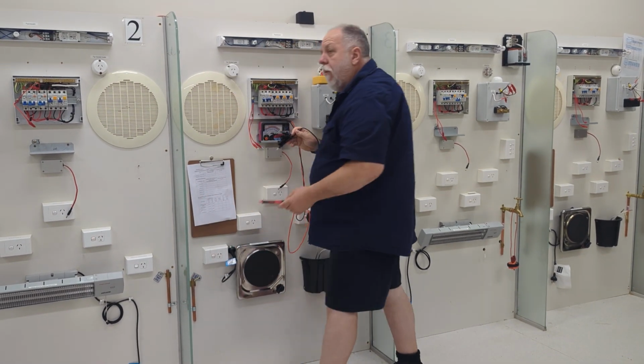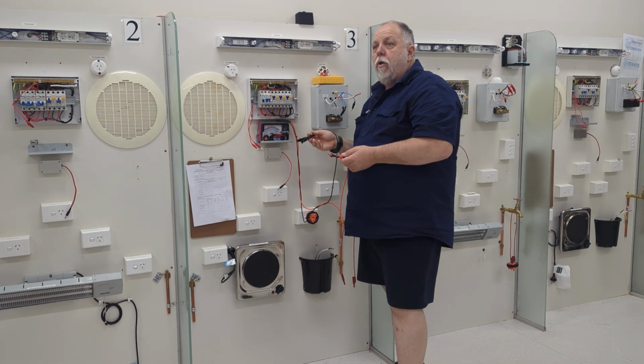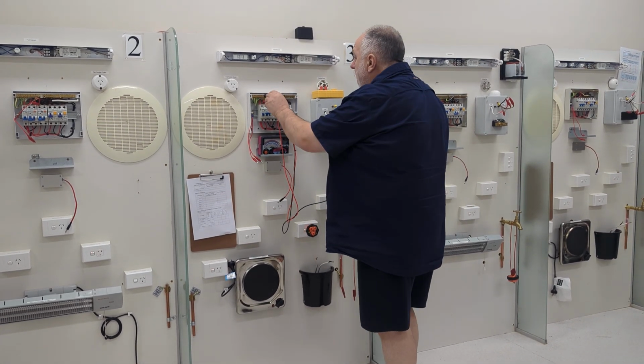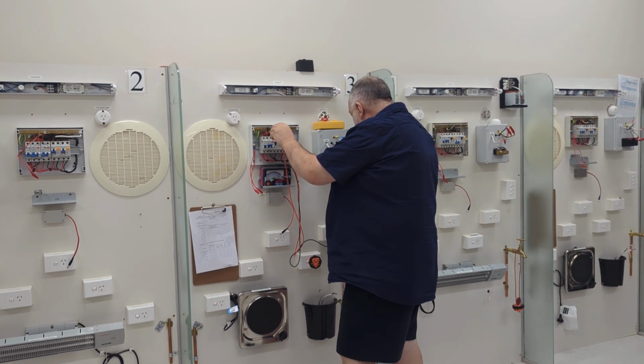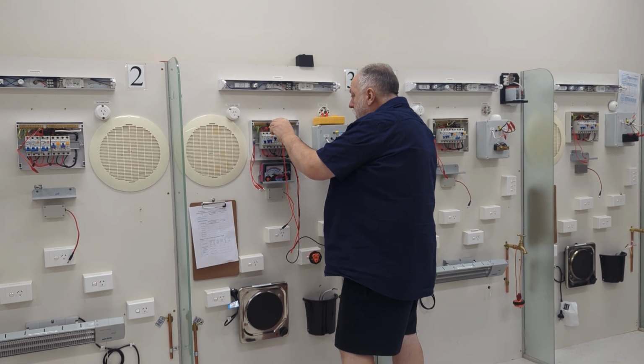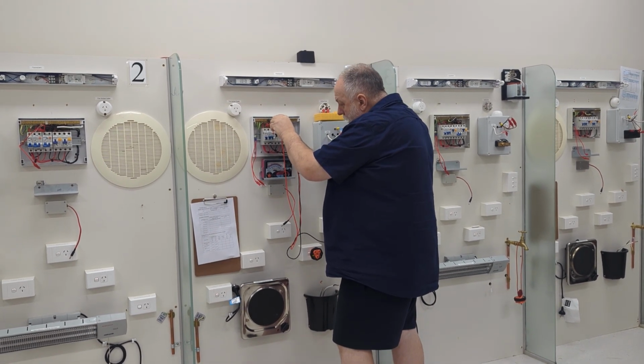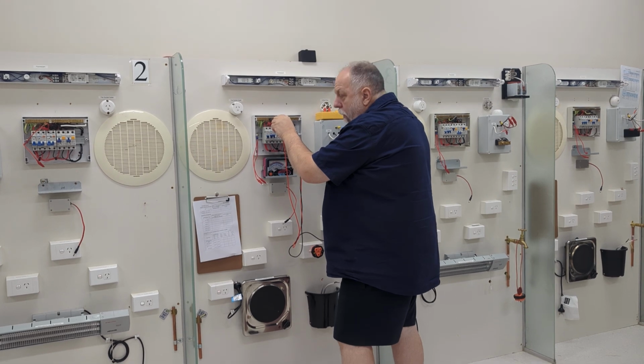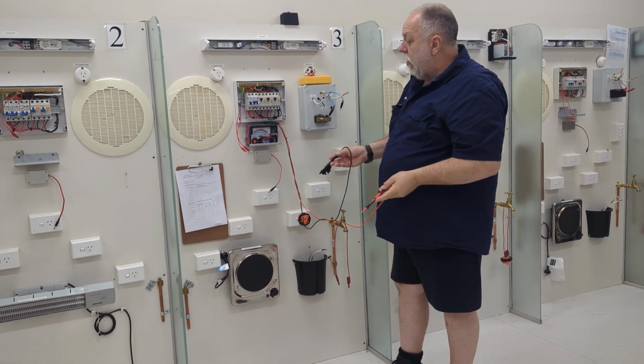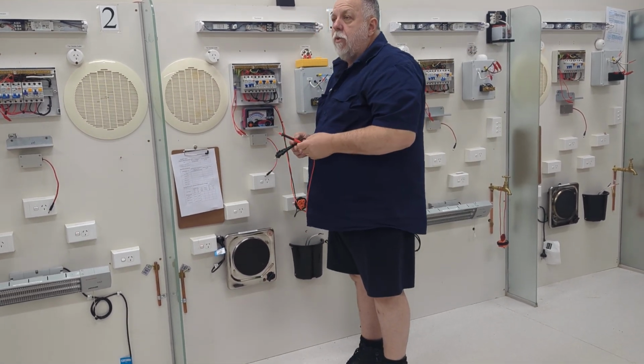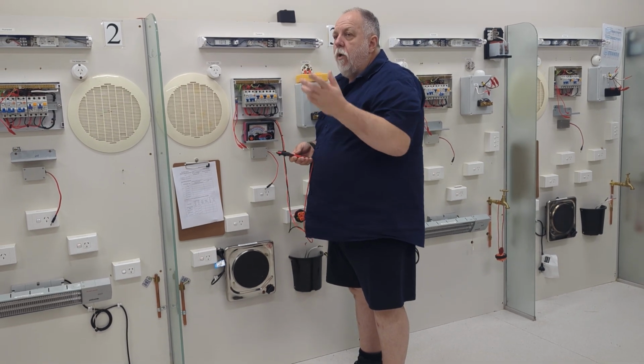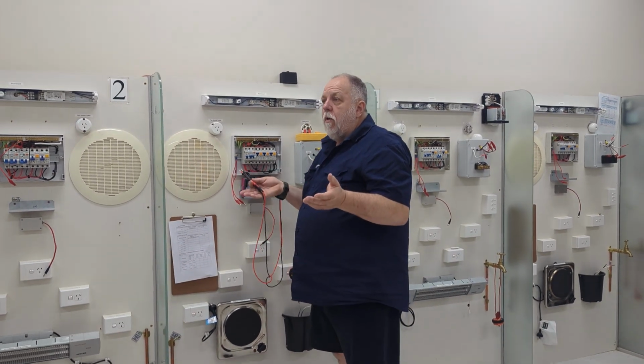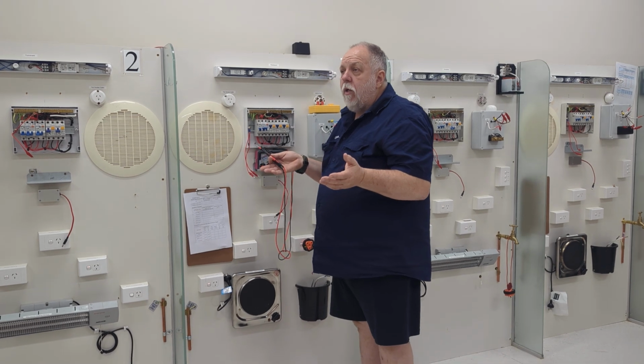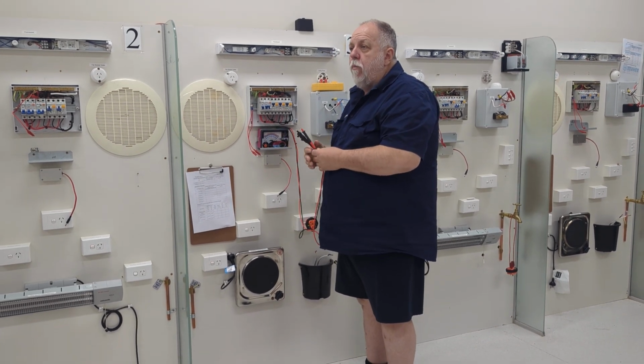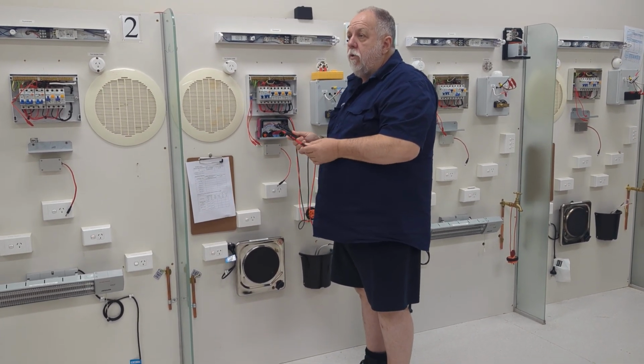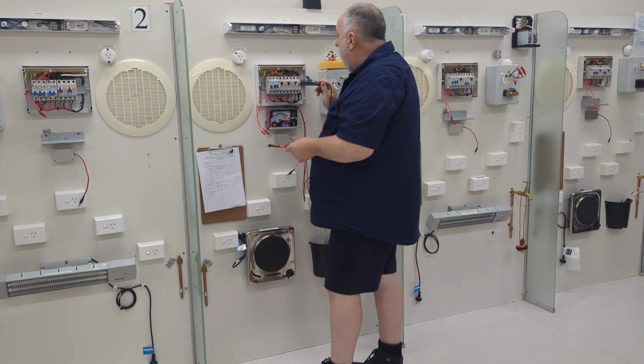I'm getting nothing there. That tells me that I've got an open circuit, there's nothing there. Now I'll go from the main earth down to the earth bar to my bonding conductor. I've got a reading here, it's about 0.1, that's okay. So on your sheet, you would have that the main earth is an open circuit. Don't write infinity because you're not measuring voltage or anything. Just say it exceeds the 0.5 ohms. It's not reading anything at all.